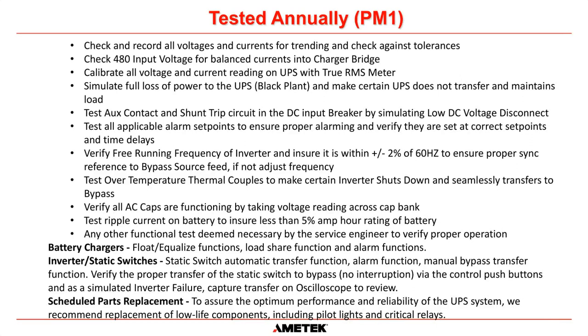We also verify all AC caps are functioning by taking voltage readings across the capacitor bank. This is more specific to our ferroresonance systems. The AC capacitors in the tank circuit, we want to make sure that they are working. Not only do we take voltage readings, we take current readings as well. We test the ripple current into the battery to ensure that it's less than 5%. And we also compare it to the last reading we took to make sure that the ripple current isn't changing. If it changes, then that's indicative of a battery failure or maybe a capacitor failure.